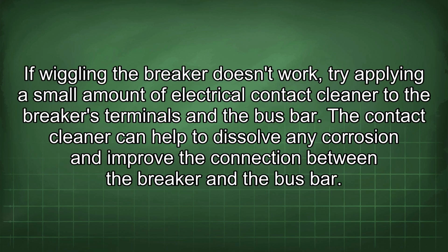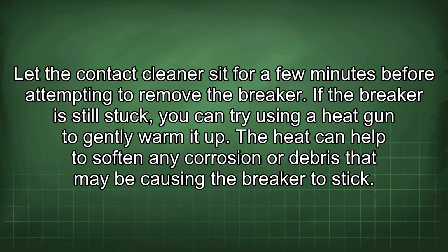If wiggling the breaker doesn't work, try applying a small amount of electrical contact cleaner to the breaker's terminals and the bus bar. The contact cleaner can help to dissolve any corrosion and improve the connection between the breaker and the bus bar. Let the contact cleaner sit for a few minutes before attempting to remove the breaker. If the breaker is still stuck, you can try using a heat gun to gently warm it up.